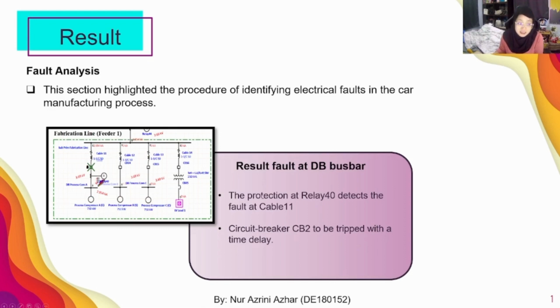As you may see here, the fault is applied in the fabrication line, which is feeder 1, and the protection at relay 40 may detect the fault at cable 11, which is after the relay location. Then the circuit breaker, which is the cross shape here, is tripped with a time delay. So this is how the fault occurs at the DB bus bar, which is the distribution board bus bar.